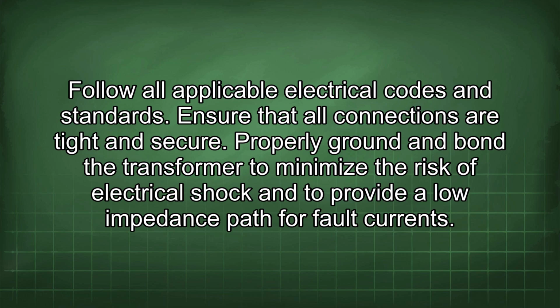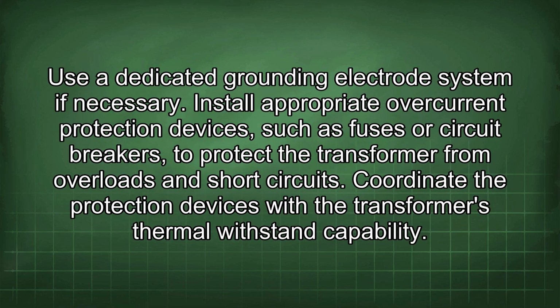Properly ground and bond the transformer to minimize the risk of electrical shock and to provide a low impedance path for fault currents. Use a dedicated grounding electrode system if necessary. Install appropriate overcurrent protection devices, such as fuses or circuit breakers, to protect the transformer from overloads and short circuits. Coordinate the protection devices with the transformer's thermal withstand capability.